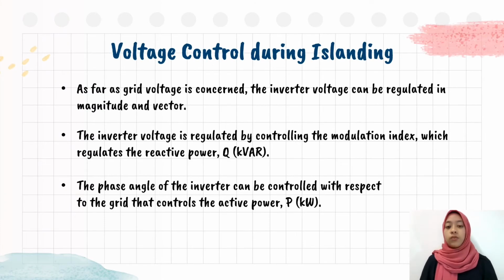Next, moving to voltage control during islanding. As far as grid voltage is concerned, the inverter voltage can be regulated in magnitude and vector. The inverter voltage is regulated by controlling the modulation index, which regulates the reactive power Q. The phase angle of the inverter can be controlled with respect to the grid, which controls the active power P.